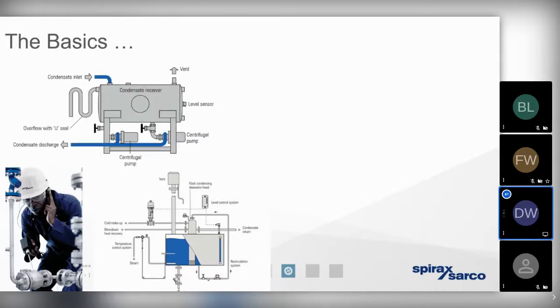So we've mentioned we want to recover as much of the condensate as possible, meaning we want to have a correctly sized, selected and installed condensate recovery pump. We know that a condensate recovery pump, especially when it's electrically configured, can only move condensate when it's a single phase liquid at a temperature of 97 degrees or less, which means that a fall in pressure is going to result in flash steam losses at the vent. We'll come on to how we can address that in a few slides' time.